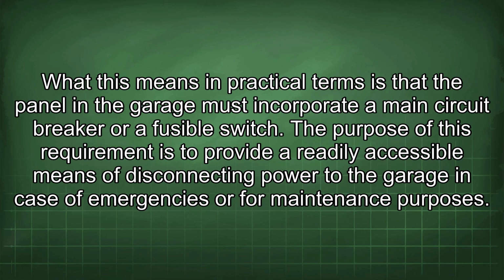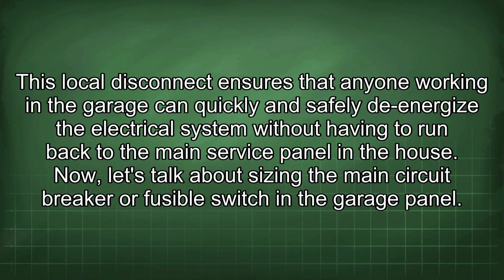The purpose of this requirement is to provide a readily accessible means of disconnecting power to the garage in case of emergencies or for maintenance purposes. This local disconnect ensures that anyone working in the garage can quickly and safely de-energize the electrical system without having to run back to the main service panel in the house.